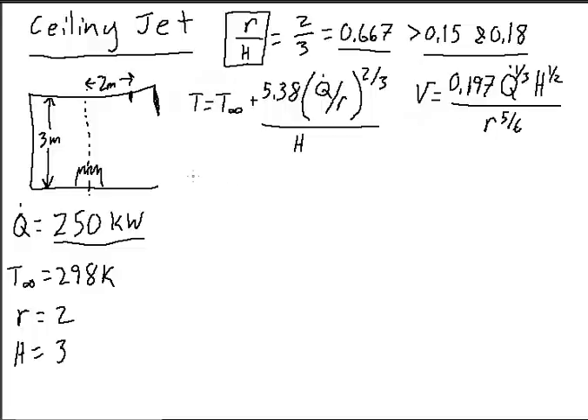So to find the temperature, with this value being greater than both 0.15 and 0.18, we're going to use this equation to find the temperature and this equation to find the velocity. In the velocity equation, in the third version of the SFPE Handbook, this number was 0.195, so I assume the new version is correct.